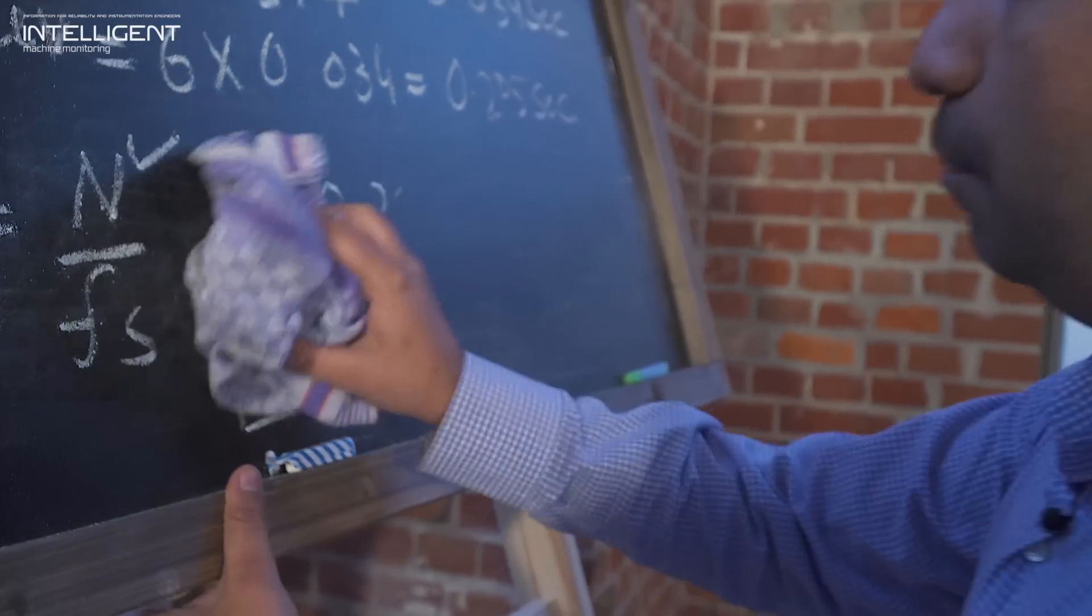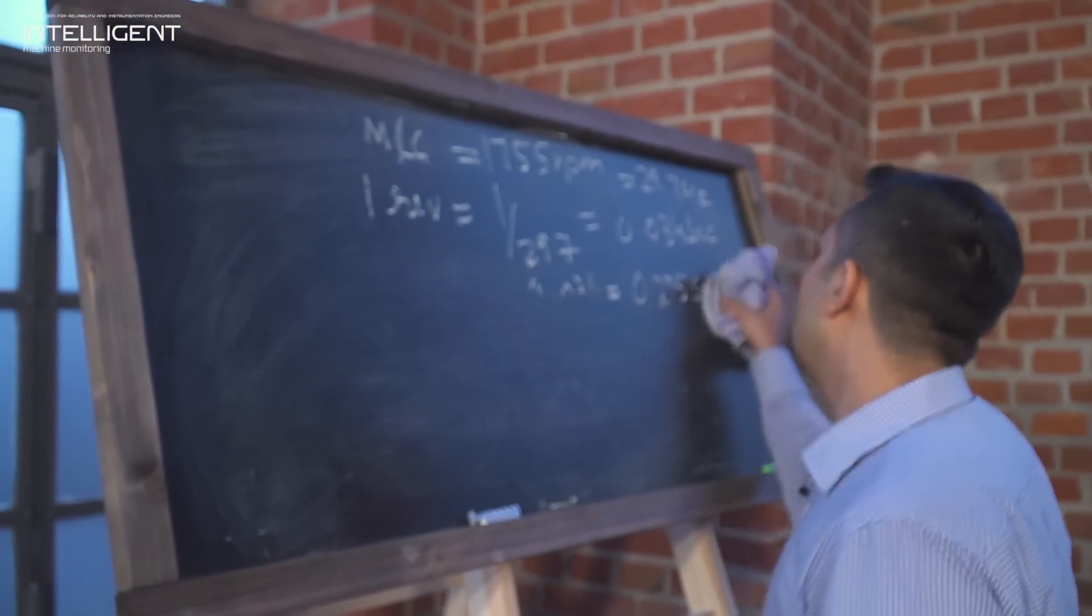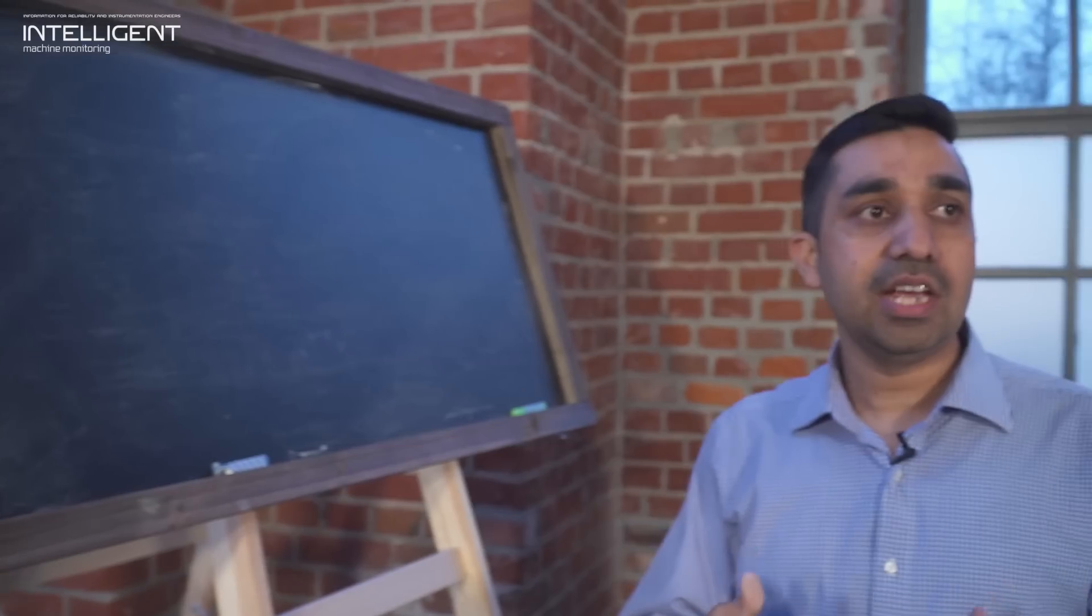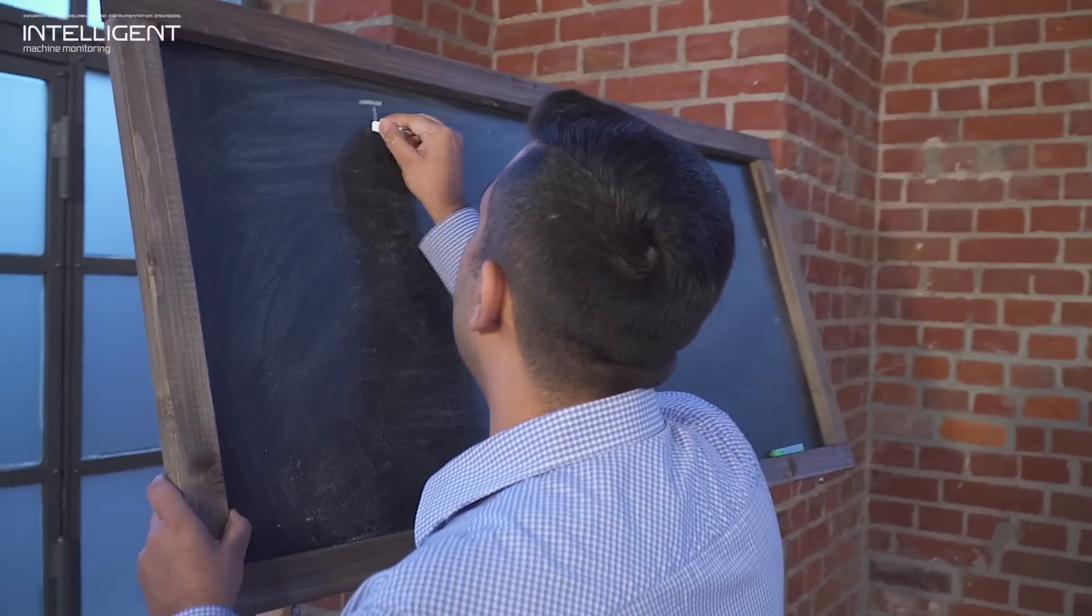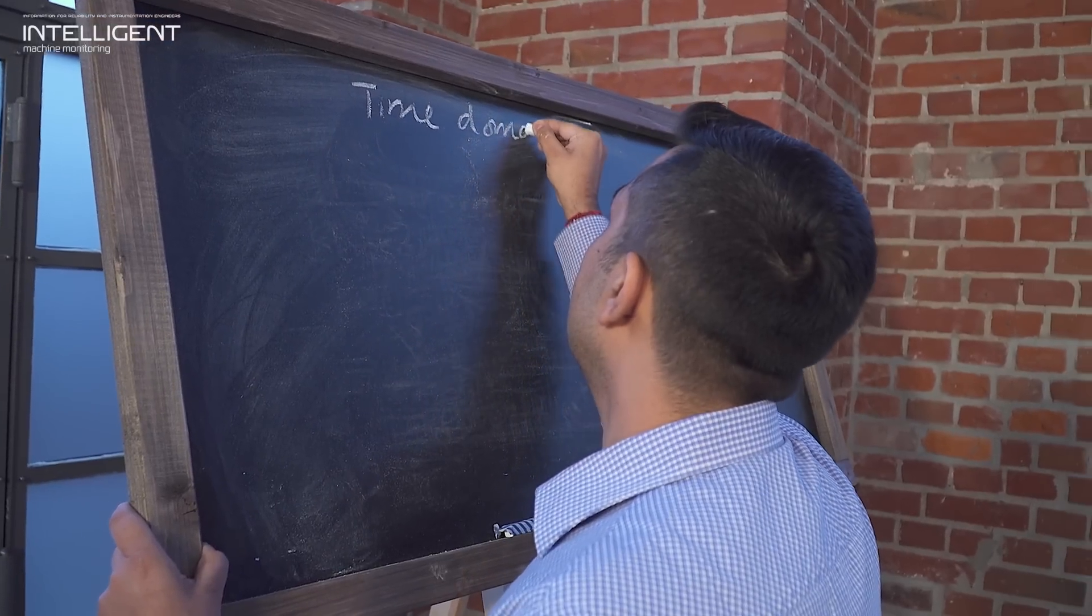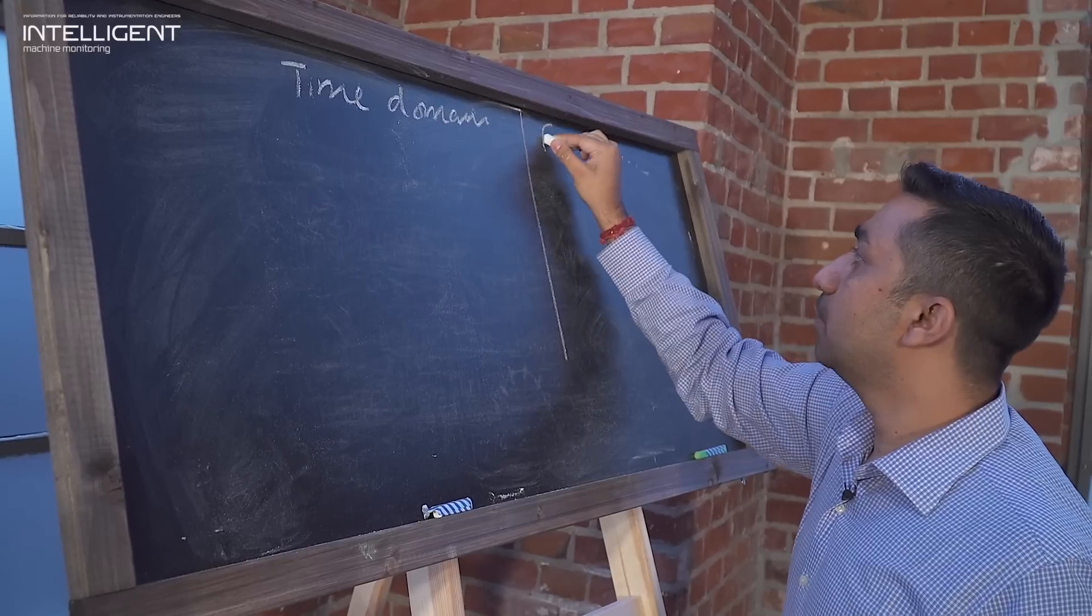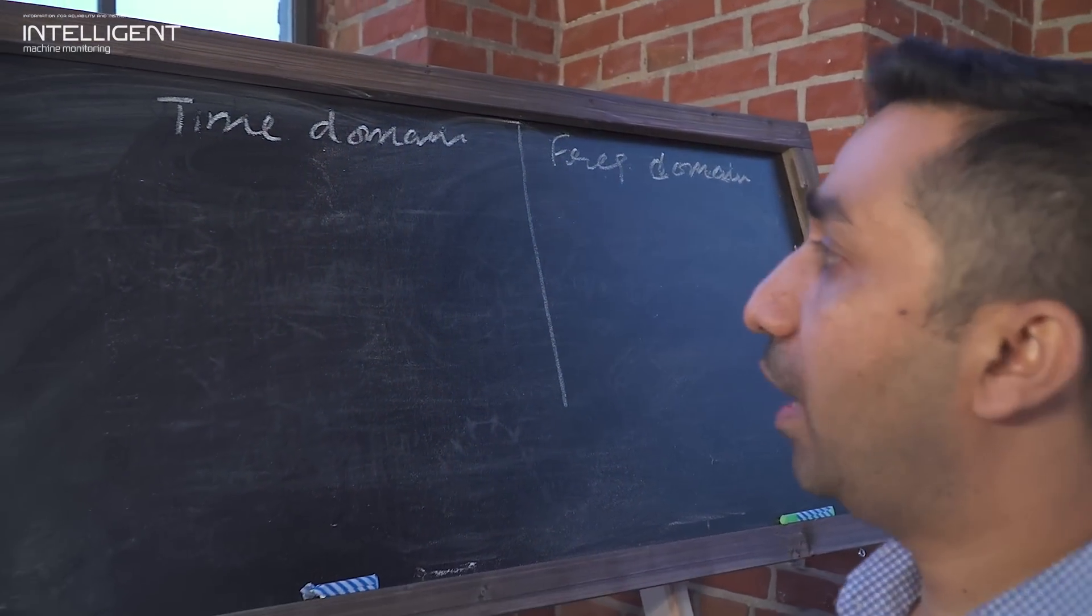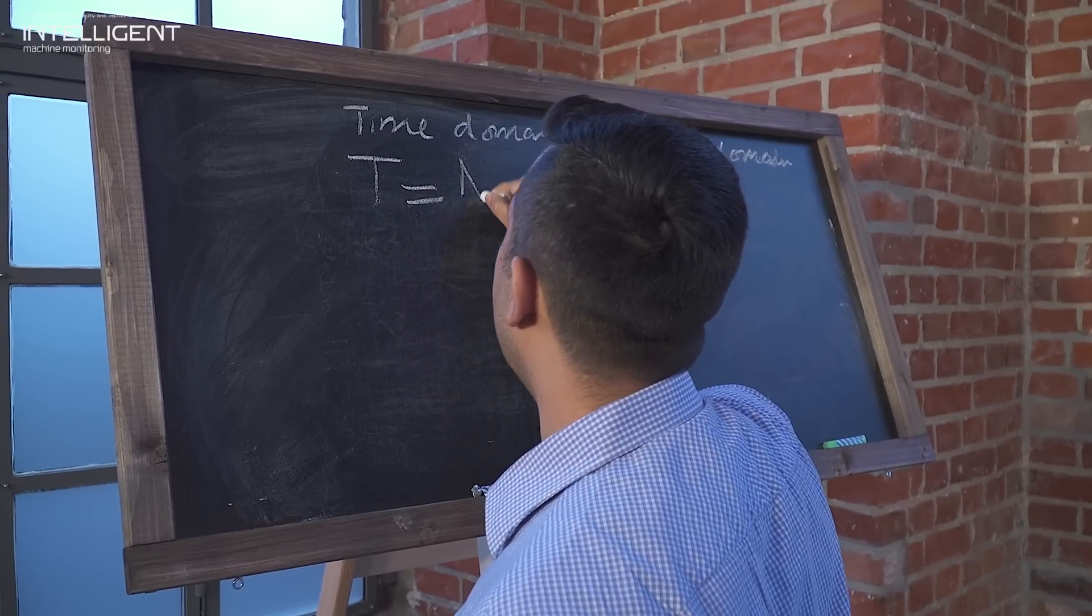If you have two of these parameters among three, you can calculate the other one. In most of the analyzers, most of the systems, you have an option to select time and number of samples. And the sampling rate would be calculated automatically, keeping in mind that you need to capture six revolutions and this many number of samples. So, now our aim is to compare these three parameters which we defined in time domain and to correlate these settings in frequency domain.